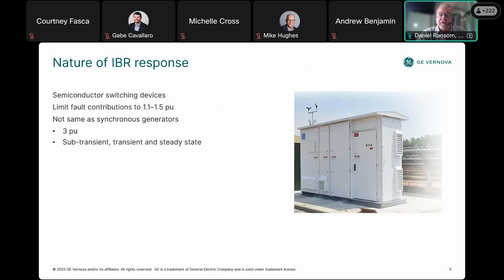The nature of inverter-based resources response is a little bit quirky because IBRs use semiconductor switching devices that have control algorithms to protect against outputting large currents. These would destroy the semiconductor IGBT output devices. Typically, IBRs limit the fault current to 1.1 to 1.5 per unit of the inverter nominal current rating. IBRs do not produce the large fault currents that are typical of utility sources of synchronous generators.